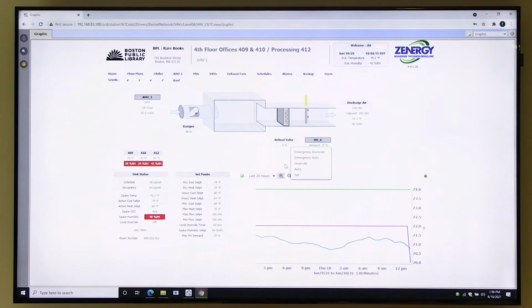If after minutes it doesn't update, then maybe there was an override in there that never got cleared behind the scenes or something. Or it's just something to keep in mind that there is a delay when reading the points from the screen.